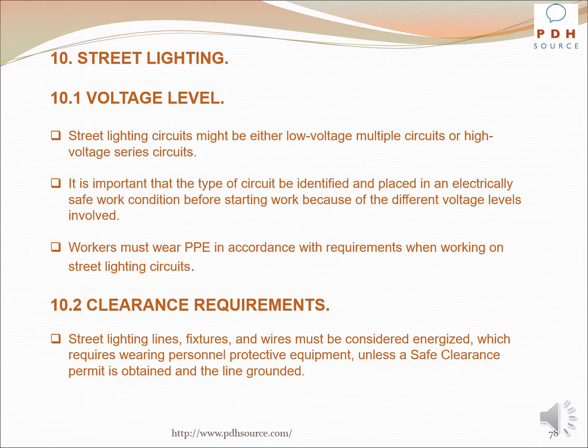With regard to street lighting, the voltage level street lighting circuits might be either low voltage multiple circuits or high voltage series circuits. It's important that the type of circuit be identified and placed in an electrically safe work condition before starting work because of the different voltage levels involved. Workers must wear personal protective equipment, PPE, in accordance with the requirements when working on street lighting circuits. Street lighting lines, fixtures, and wires must be considered energized, which requires wearing personal protective equipment unless a safe clearance permit is obtained and the line grounded.